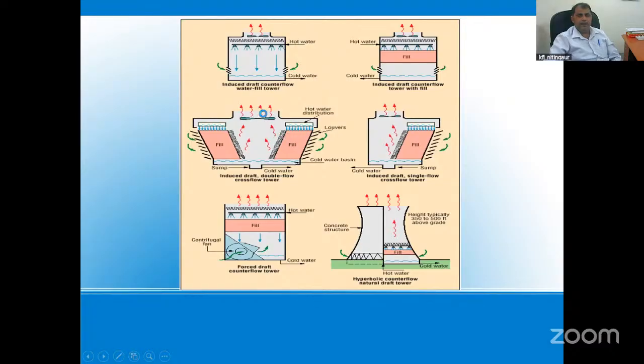Then it passes through what is called the drift eliminator. This area is called the drift eliminator. The purpose of the drift eliminator is to reduce drift loss. Drift loss means the entry of water particles along with the water vapors. So these are the different types of cooling tower, in which the most commonly used is the induced draft double flow cross flow tower, and this is in the KFL also.